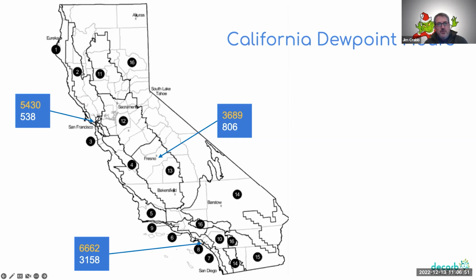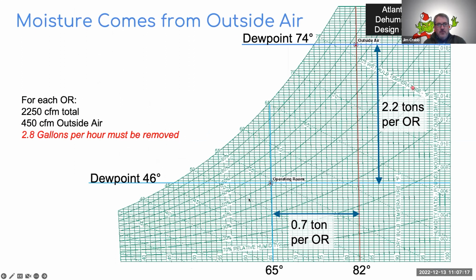The dew point temperature at 75 degrees and 50% relative humidity is about 55 degrees. And the dew point temperature at 65 degrees and 50% relative humidity is 46 degrees. Those are the operative numbers for figuring out whether you're delivering the right and maintaining the right conditions in a space. So you see an awful lot of California.